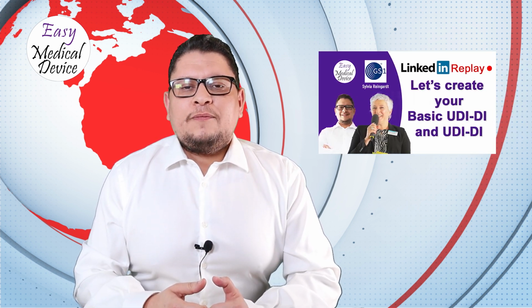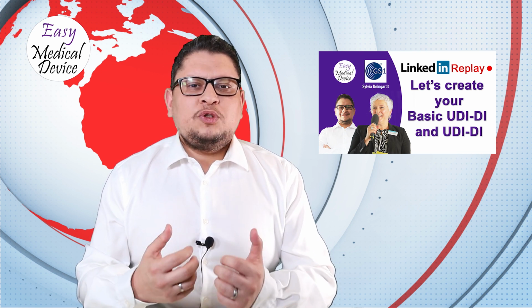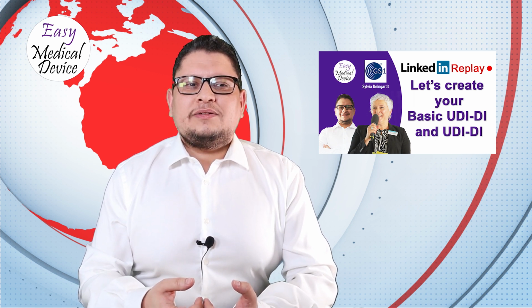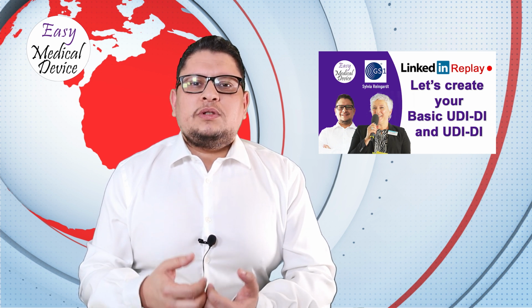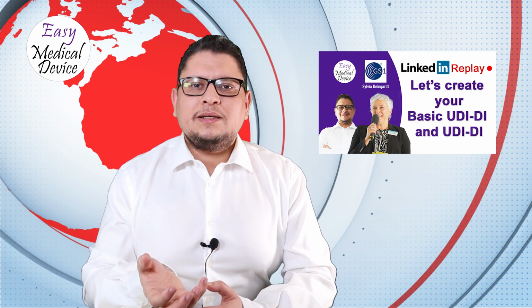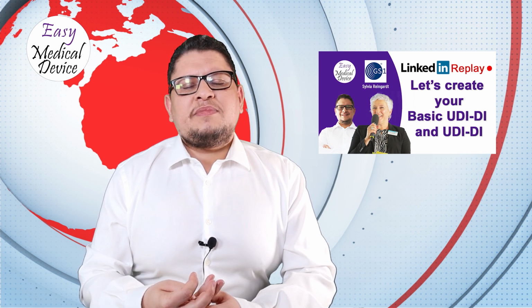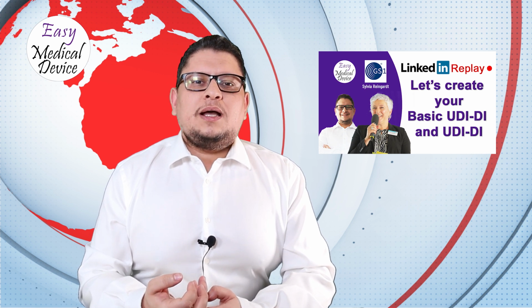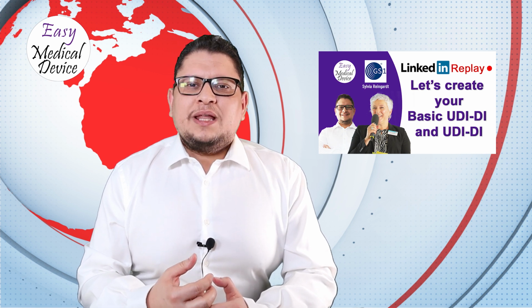The second live was with Sylvia Reingart from GS1, where we helped companies that still don't have a UDI number under MDR to create one. Sylvia showed us some examples for creation of a UDI-DI and for creation of a Basic UDI-DI. This is something that every manufacturer will have to do under EU MDR, and if you don't know how to do that, this video will show you everything. I really hope this will help you.